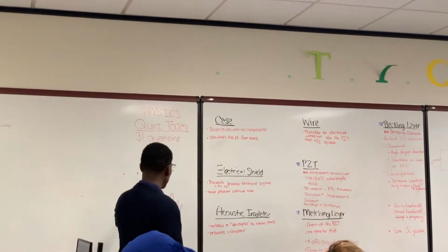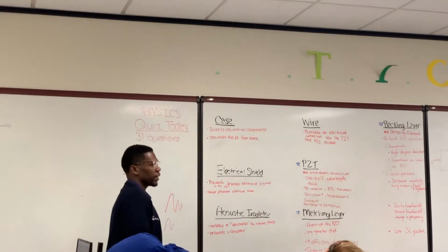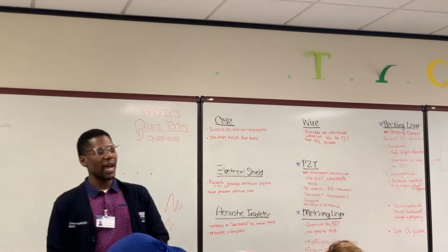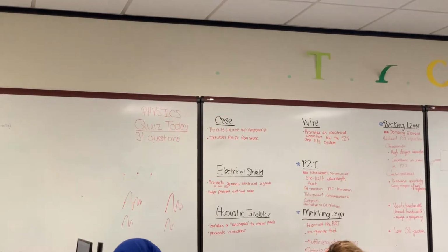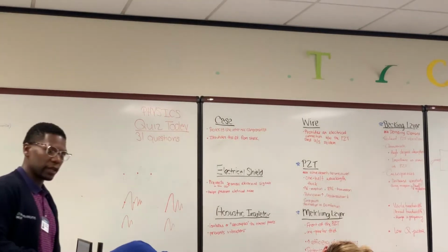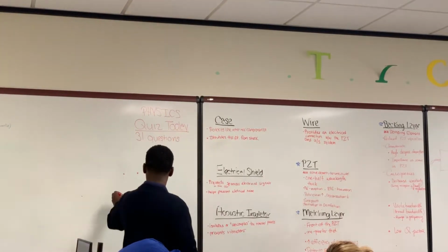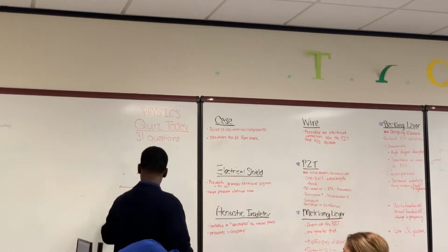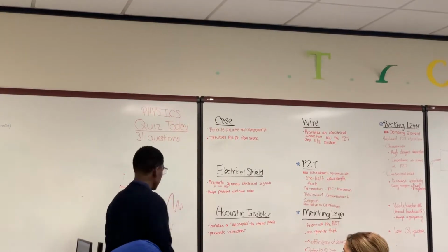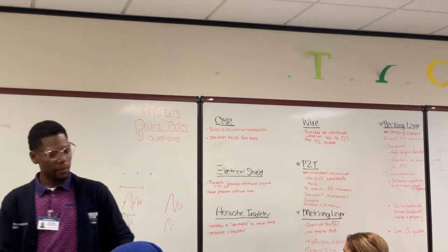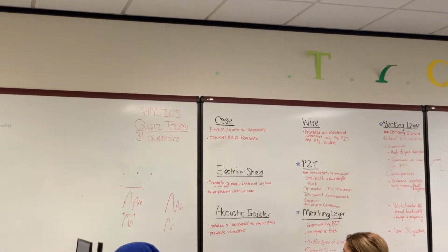So looking at these two pulses, these two waves right here, which one of those will provide us with better axial resolution? The bottom one, right? Because the spatial pulse length is short. The length of this pulse from here to here is short. That's going to have better axial resolution. So axial resolution is determined by the spatial pulse length. We're kind of getting into that a little early, but axial resolution is determined by the spatial pulse length.